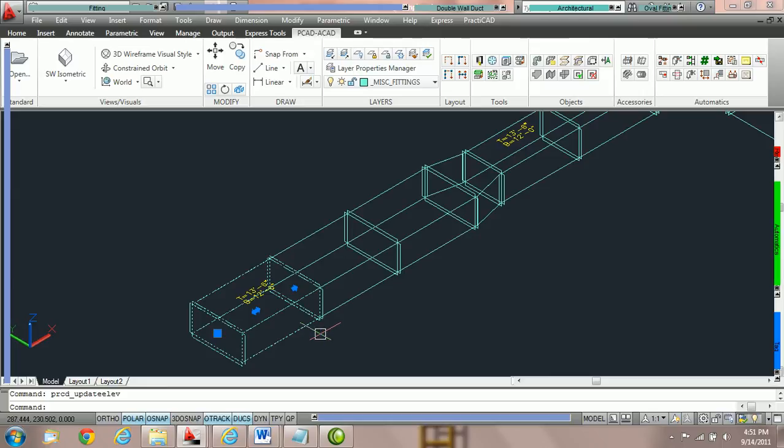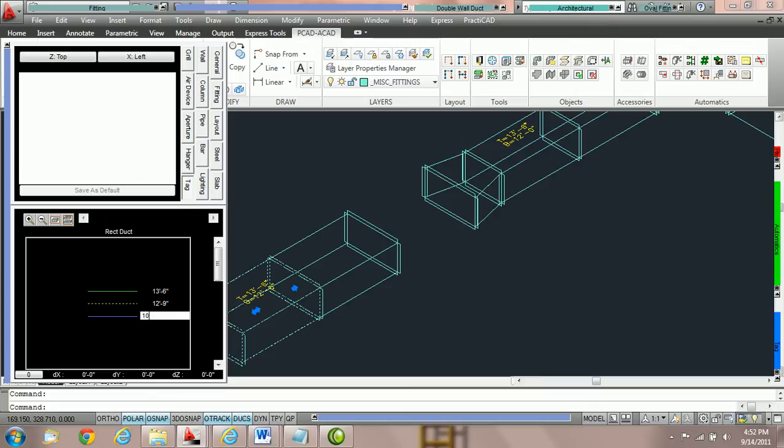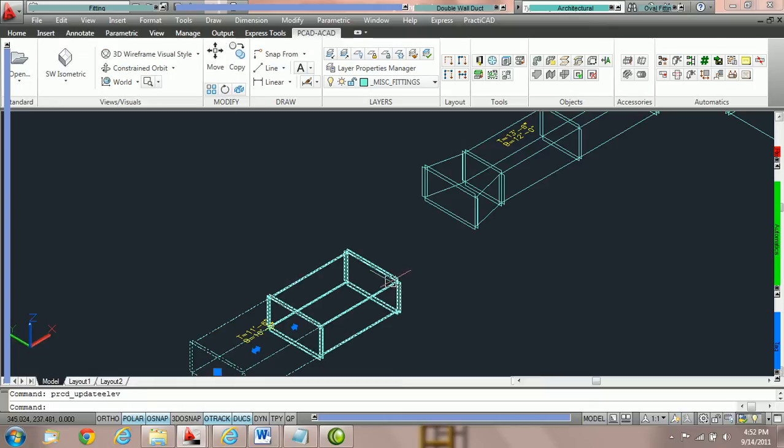Now if we wanted just 1 or 2 fittings to edit or move an elevation and not carry the rest of the duct line, we must break the duct line. For example, if we want to just move up fitting 1 and fitting 2 and not the third fitting, we would actually delete the third fitting. Then we click at the beginning of the duct line we want to change, and then we would make the change, let's say back down to 10 foot. Then we'd of course use an auto route or a single to attach the duct line, but the idea is we've only moved the specific section of duct we want. If it's connected, it's going to edit all the way forward or backwards in the duct line.